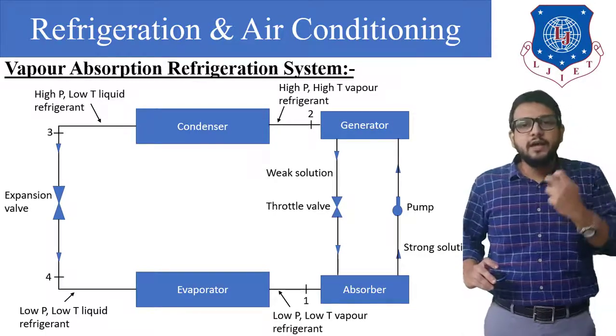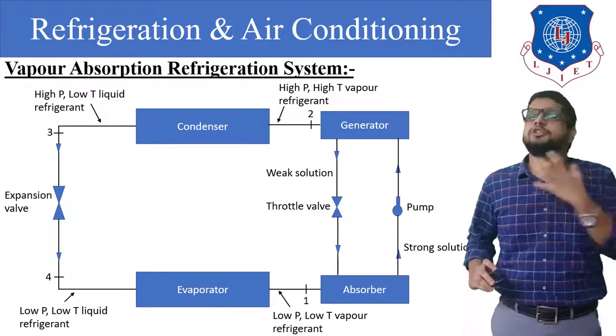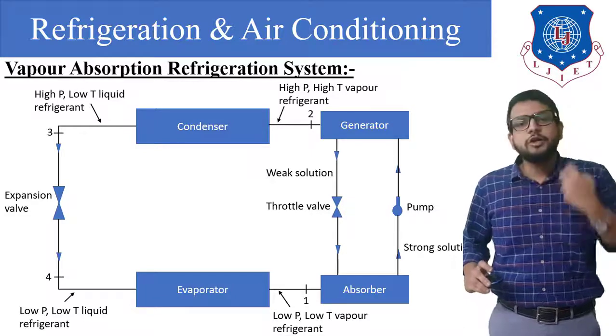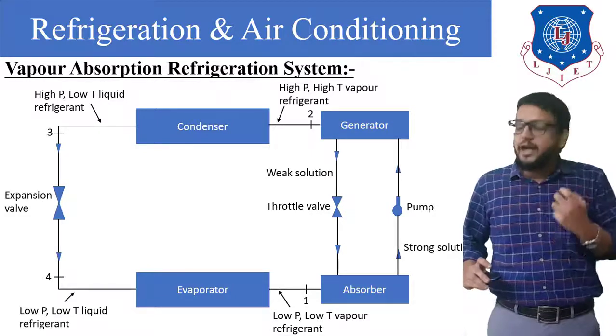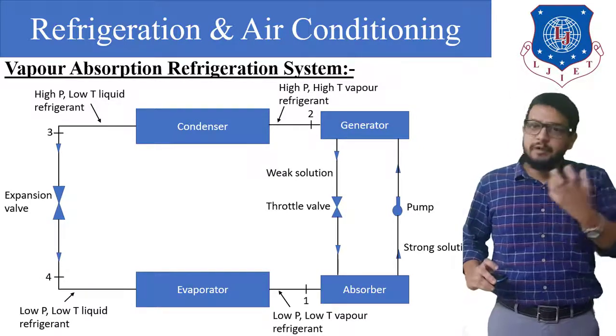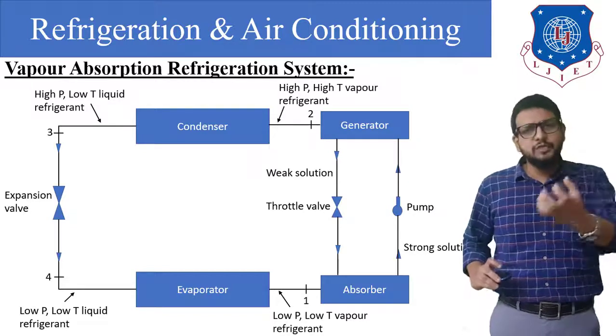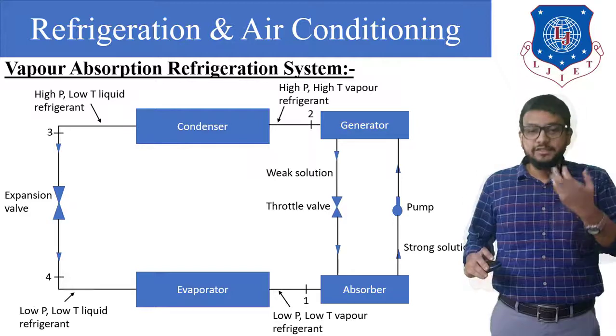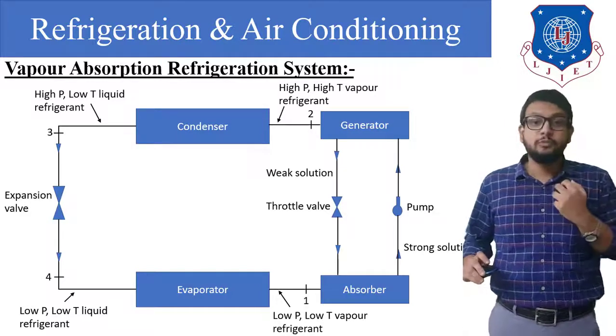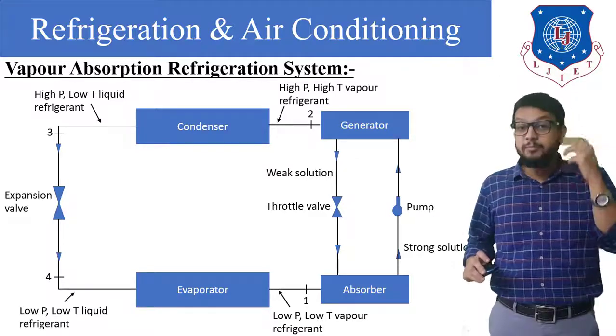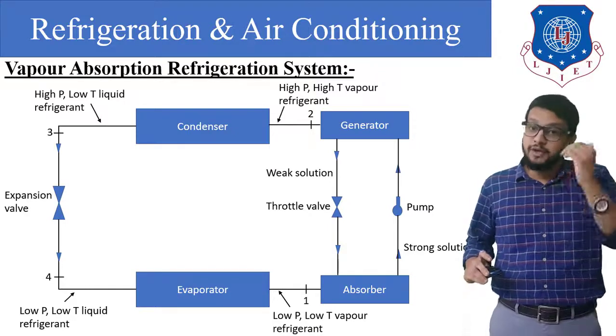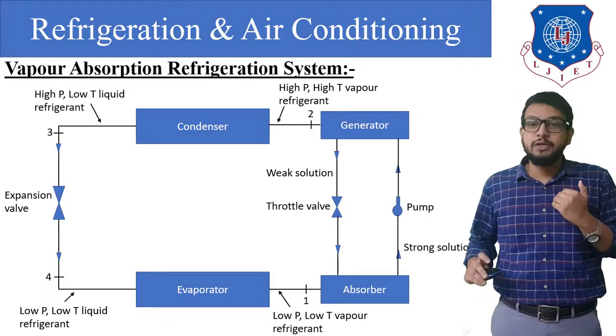The new component is the absorber. Inside the absorber we place cold water. As soon as the ammonia refrigerant enters the absorber, it dissolves in the cold water and is absorbed — hence the name absorber. The function of the pump is to increase the pressure up to condenser pressure and supply the solution to the generator.